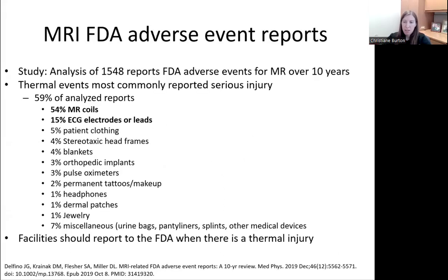So of all the MR safety issues, why the focus on thermal injuries? Well, in a 10-year study, the FDA received and analyzed around 1,500 adverse event reports for MR systems between the 1st of January 2008 and the 31st of December 2017. It turns out that thermal events were the most commonly reported serious injury, comprising 59% of analyzed reports.